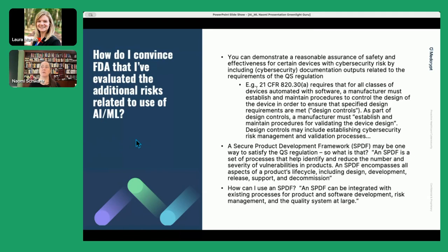That's the big discriminator. So how do I convince FDA that I've evaluated all these additional risks? What is the necessary documentation? Well, you need to demonstrate a reasonable assurance of both safety and effectiveness now, and security. You need to talk about your security risk management deeply. It goes beyond 21 CFR 820.30A, requiring that all devices established with automation, with software, have design controls.